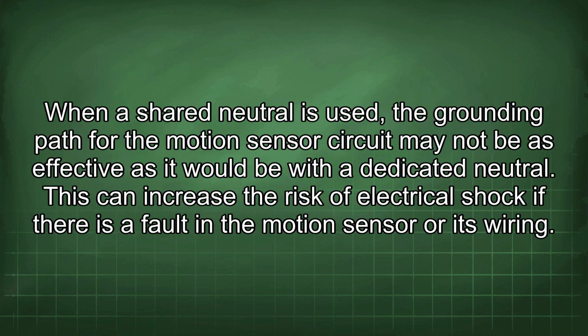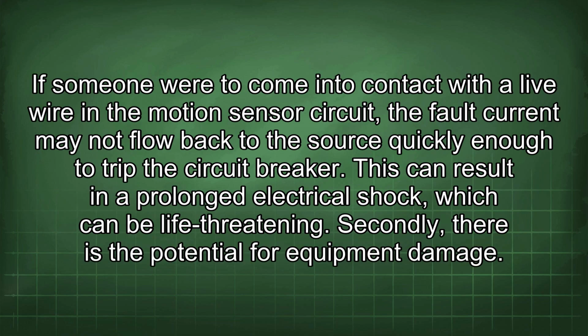When a shared neutral is used, the grounding path for the motion sensor circuit may not be as effective as it would be with a dedicated neutral. This can increase the risk of electrical shock if there is a fault in the motion sensor or its wiring. If someone were to come into contact with a live wire in the motion sensor circuit, the fault current may not flow back to the source quickly enough to trip the circuit breaker. This can result in a prolonged electrical shock, which can be life-threatening.